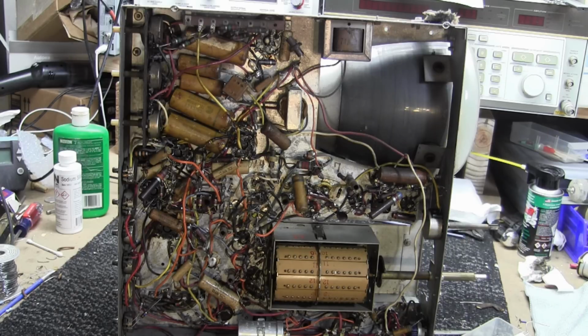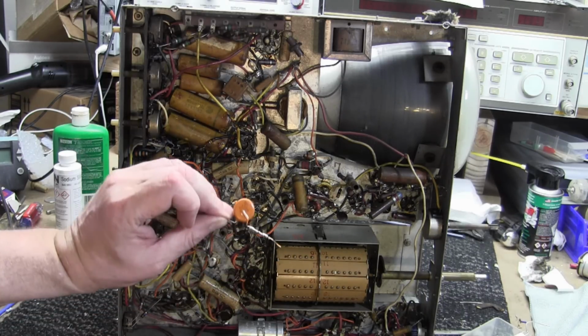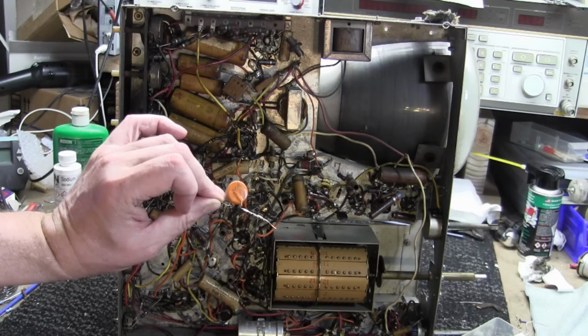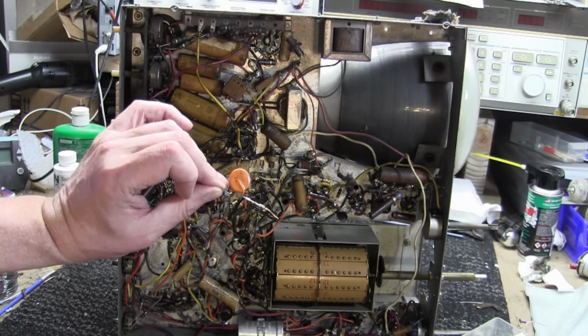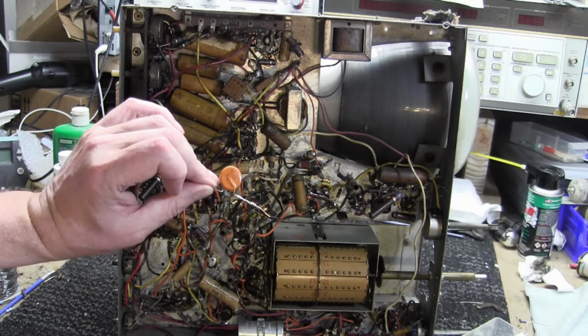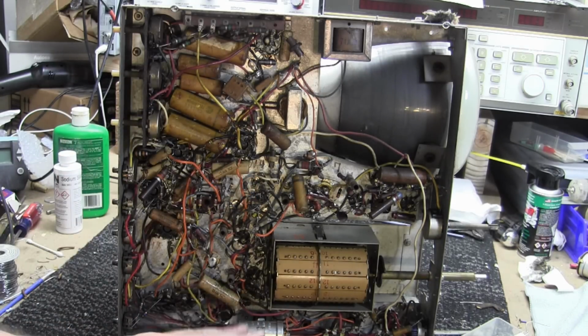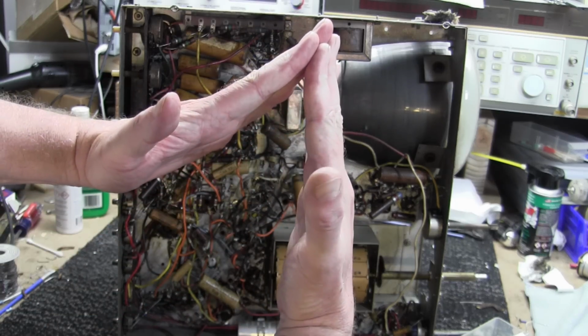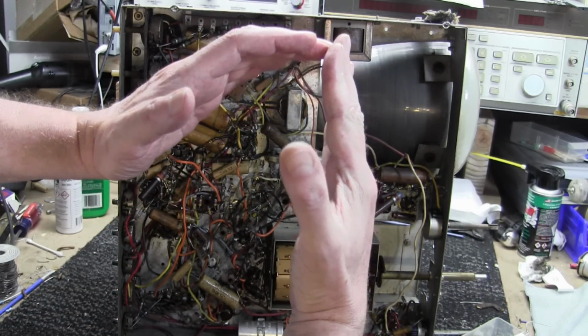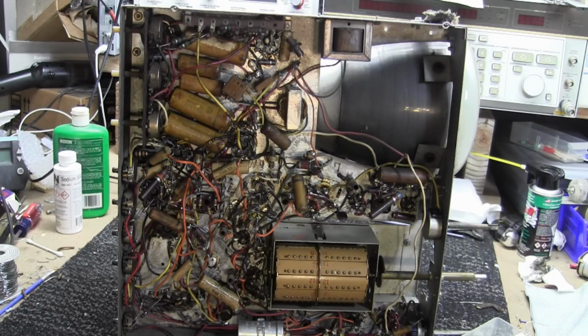The other issue, a much bigger one, is the dielectric constant changes with applied voltage. By the time you're up to 6,000 volts, the capacitance has changed considerably. So instead of a nice sharp sawtooth, it's going to be bent at the top. It will be very noticeable on your resulting image as bad linearity, more on the vertical than the horizontal, because it's lower frequency and more sensitive to changes in capacitance.